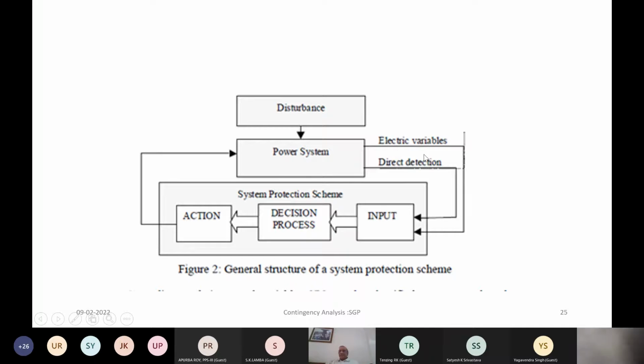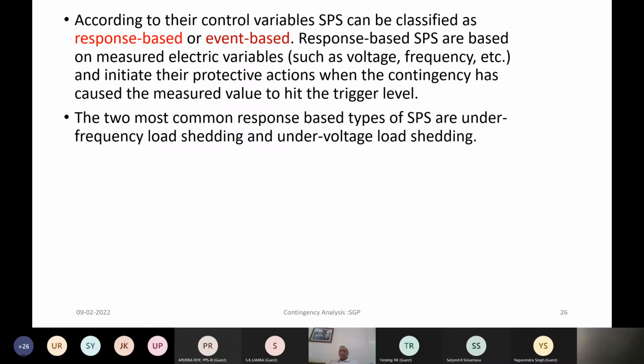And these signals become input. Then there is a decision-making process, and there is a remedial action, which is again implemented in the power system using the existing SCADA systems for implementation of actions. So these are called response-based or event-based. Response-based means certain parameter exceeding some limit. Event-based is say tripping of tie line or bus fault occurring at some station.